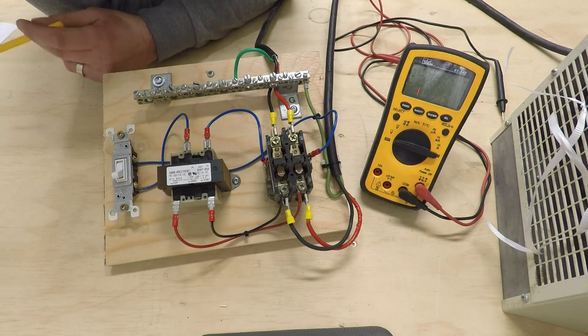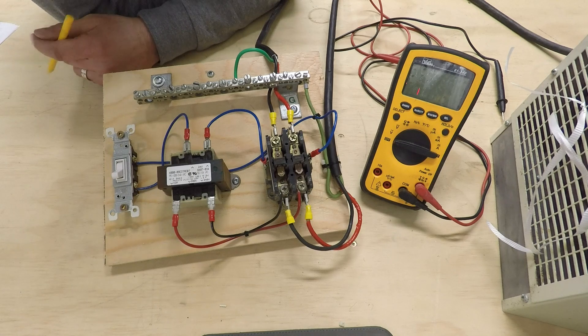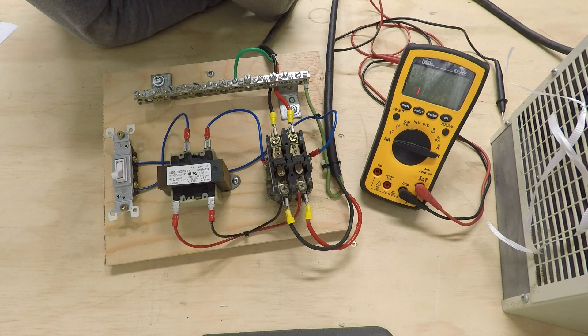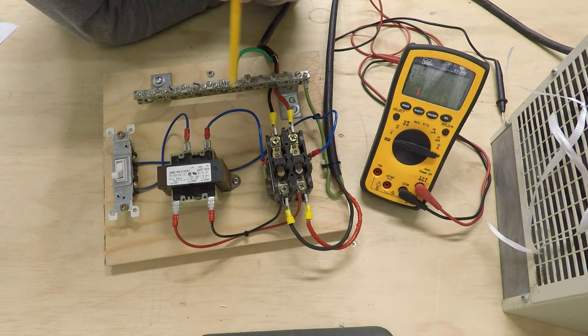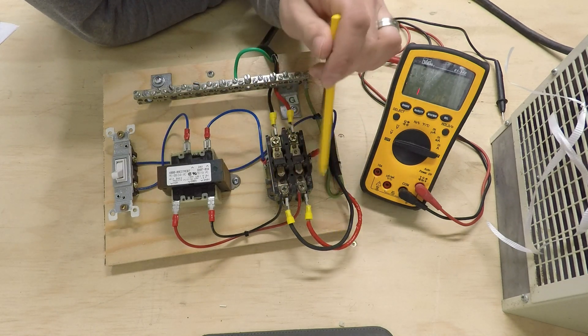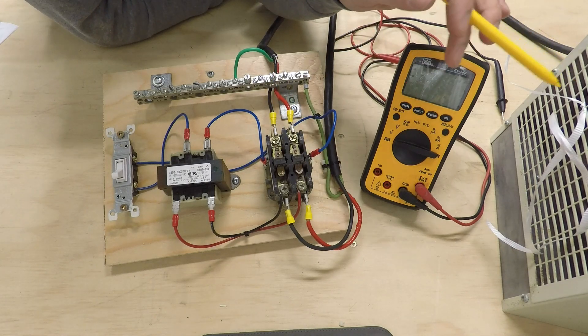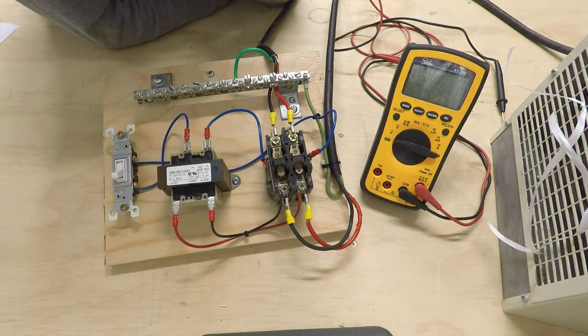This video I'm going to show you about troubleshooting a contactor you typically see used in an HVAC unit to control the turning on and off of the compressor. So I got a little test jig set up here. I've got 240 volts coming into the top of the contactor. At the bottom side of the contactor I've got it hooked up to a 240 volt rated fan to kind of simulate the compressor.